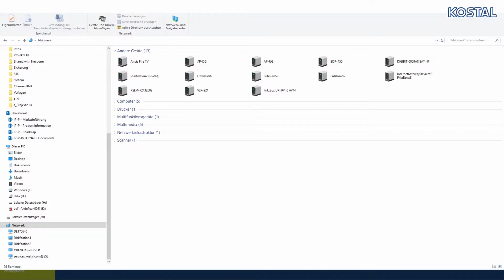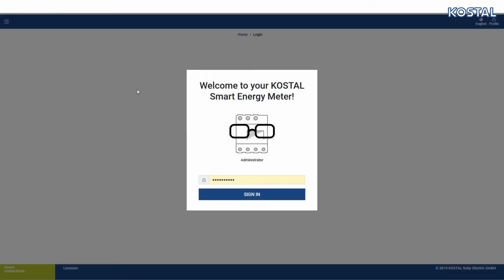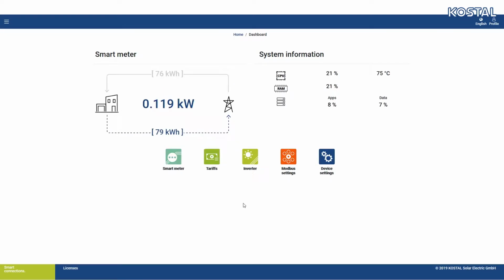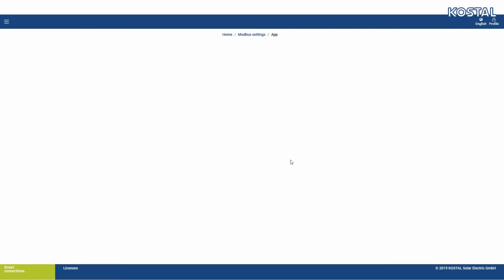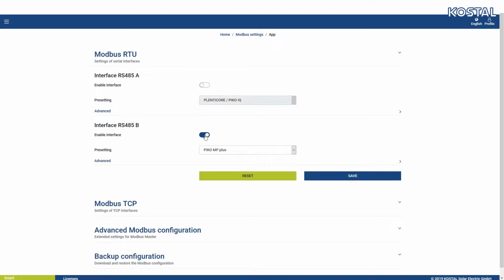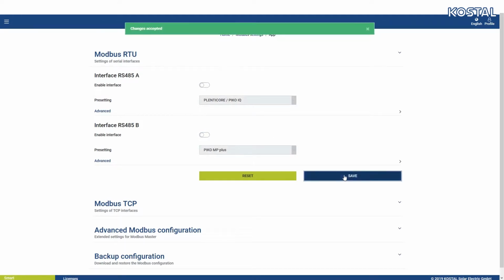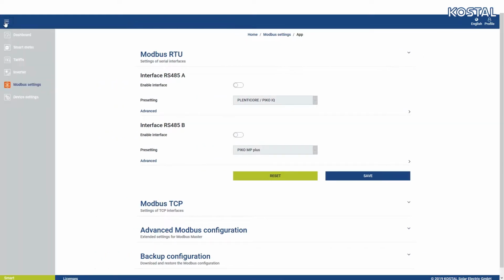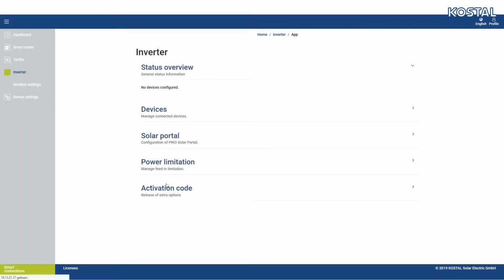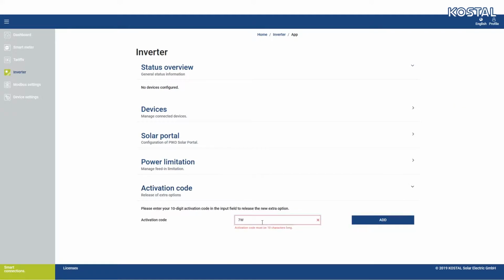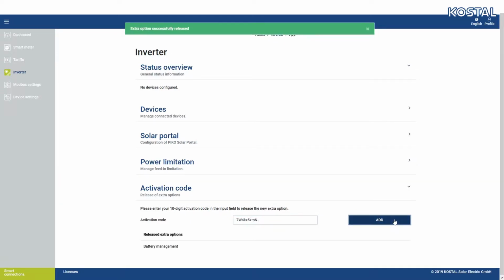Now open the KOSTAL Smart Energy Meter's web server. Do this by going to Devices and File Explorer on your PC and accessing the Smart Energy Meter you can see here. First, call up menu item Modbus Settings and deactivate both Modbus ports. Save the settings. Go to Activation Code in the Inverter menu and enter the 10-digit battery code you have acquired. The battery management field then appears under Released Extra Options.